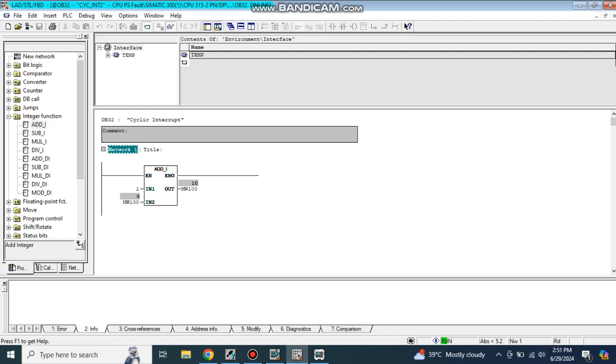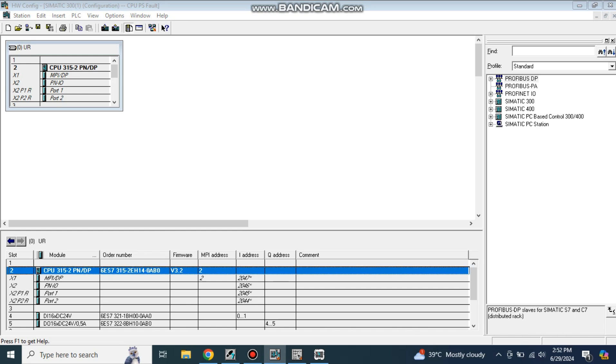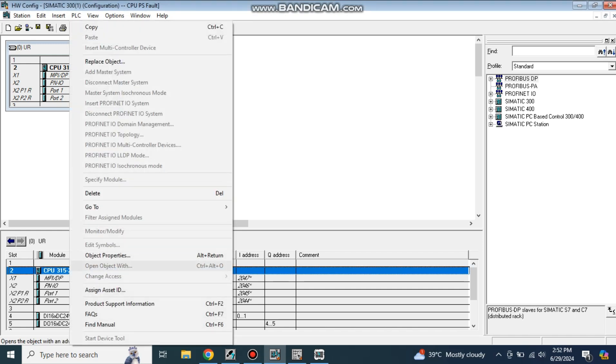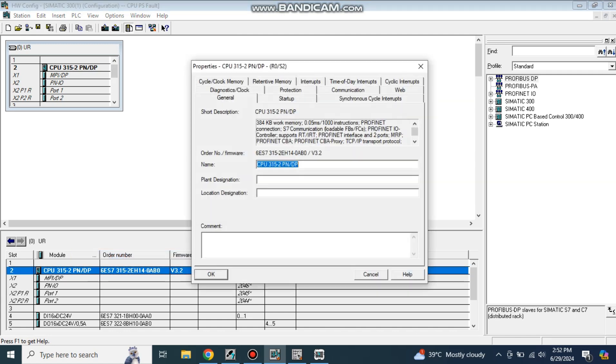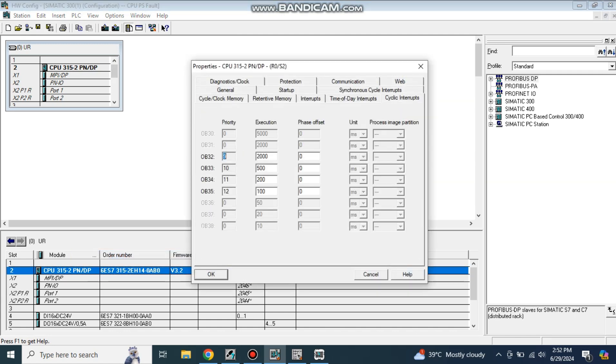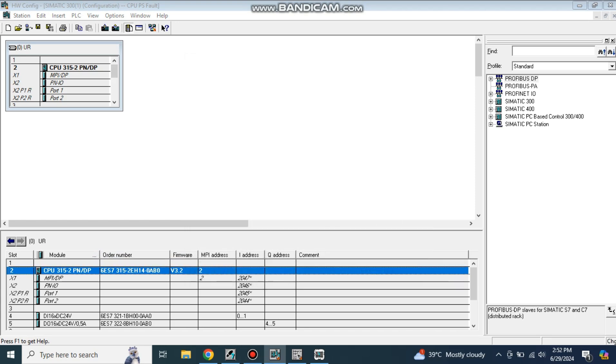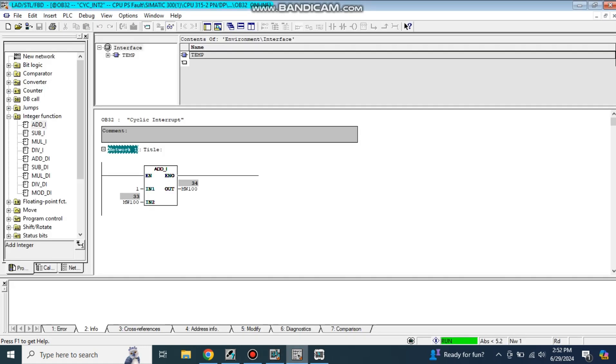So this is the way to use the interrupt OB32. But as I discussed before, OB32 is supported by my CPU which I have selected, CPU 315-2. Maybe your CPU has a different OB. For some CPUs, all the OBs from OB32 to OB38 are cyclic interrupts. You can use them depending on the CPU. You can also take OB35 and change the cyclic execution time. Some CPUs support six or some superior CPUs support all eight cyclic interrupts. Hope you like the video and understand how to use the interrupts. Especially this time we discussed the cyclic interrupt. In next video, take care.